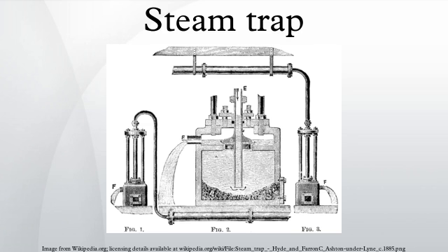The three important functions of steam traps are: discharge condensate as soon as it is formed, unless it is desirable to use the sensible heat of the liquid condensate; have a negligible steam consumption, that is, be energy efficient; and have the capability of discharging air and other non-condensable gases.